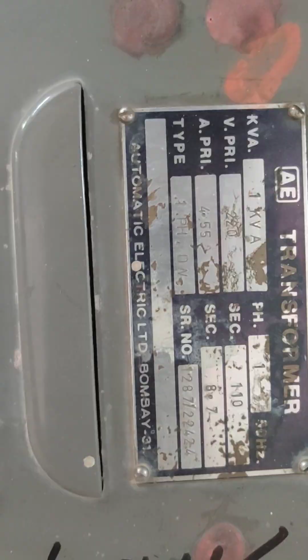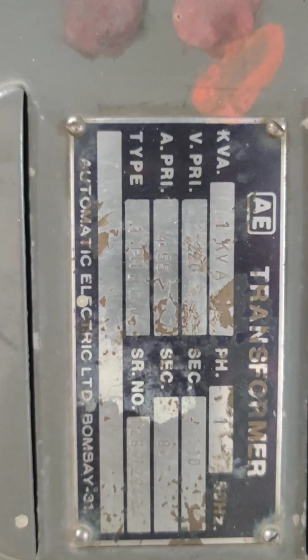Here is the 1 kVA transformer. You may identify here that it is single phase. Primary voltage is 220 volt, secondary voltage is 110 volt. Then primary current is 4.5 ampere, whereas secondary current is 8.7 ampere.